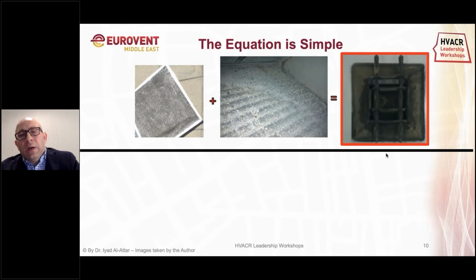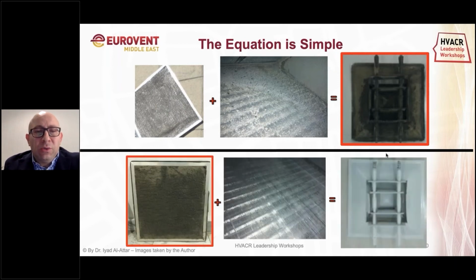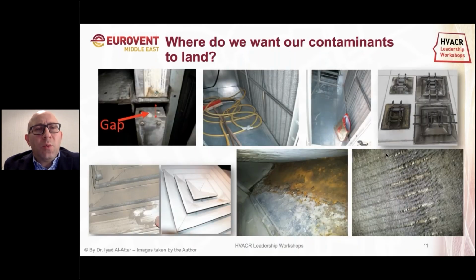This is a simple fan coil unit that I have access to, with a simple upgrade of the filter. You can see that with a very low efficiency filter, your coil participates in the filtration action, and contaminants settle on the coil, on the diffuser, and subsequently on our respiratory system. If we enhance filtration, the contaminants land on the filter instead of the diffuser, giving us a much cleaner coil and diffuser. So this is the question: where do we want the contaminants to land?